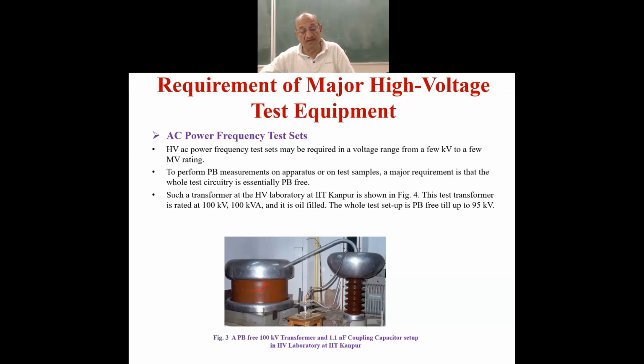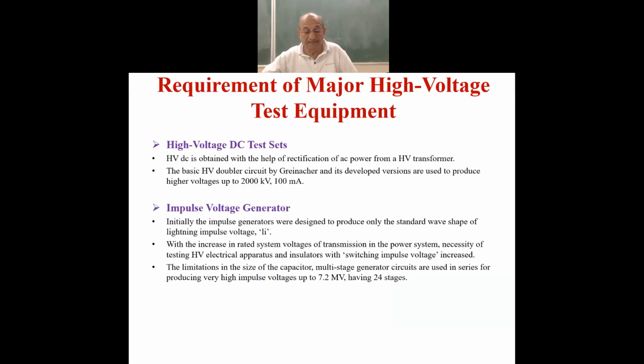To achieve PD free up to 1600 kV may be very difficult. But partial discharge measurements are not performed at such high voltage levels of the order of 1600 kV. So there would be some partial discharge activity in the very high voltage test generators, as I showed you in the previous slides. And this setup is PD free up to 95 kV. It has been verified, and we can perform the partial discharge measurements. We have learned the partial discharge measurements in the previous chapter.